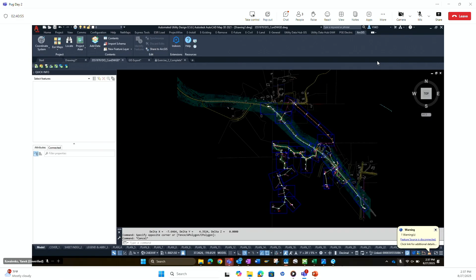So with AUD, which was a huge benefit from the designer side, we were able to generate our cable pull automatically. So our tension is automatically being calculated, our conduit length, plus we have rules that are written. If you're connected to a pad-mounted transformer, these are the tails for the cable. And if you're connected to some other piece of equipment, these are the tails. So the second number displays the tails, and then you have your tension. As soon as we were to move something, that automatically gets calculated and changed.